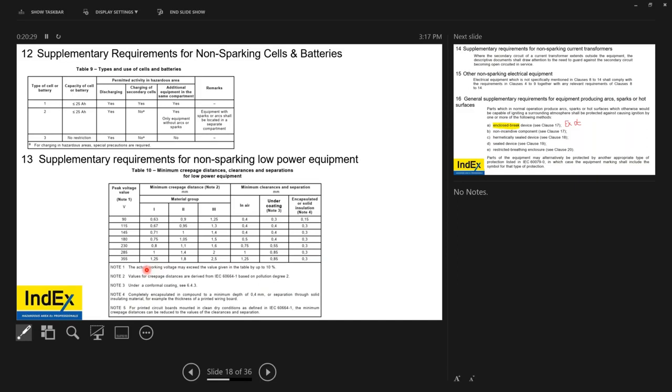Not EXNL, anything that's under 400 volts. And they're saying that the creepage and clearance distances were very small. We're talking less than 2 millimeters. So what they've done now is they've removed this, and they continue to use the creepage and clearance distance table of -7 EXE and apply it. So they've reduced the number of tables, and they removed all these things because it was overly complicated. It was just repeating steps from different standards, repeating the same tables again and again.